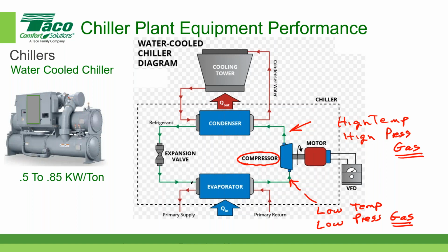So since it leaves the compressor as a high temperature, high pressure gas, it can reject its heat through a water-cooled condenser. So here's the condenser. Refrigerant is going to exit the compressor and enter the condenser at virtually the same set of conditions. And then it's going to reject its heat to the condenser water.